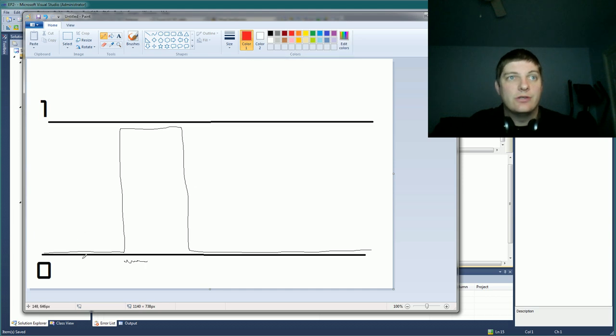So what we do now, though, is we feed this Q into the RTrig. And so the Q of the RTrig, since it's a different function type, will take that. And what it does is when its clock goes true, I'm going to draw them shifted a little bit just so you can see them. But these happen on the same scan. So when its clock comes true here, it will be on for one scan, and then its output goes off.